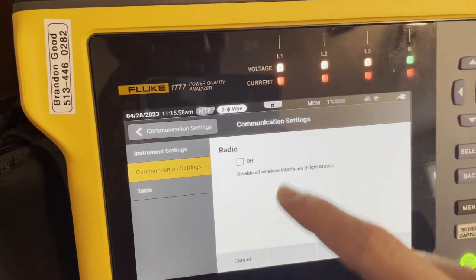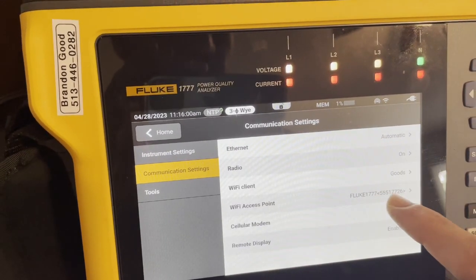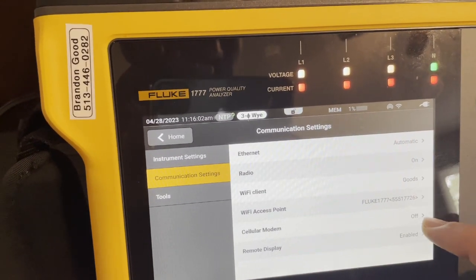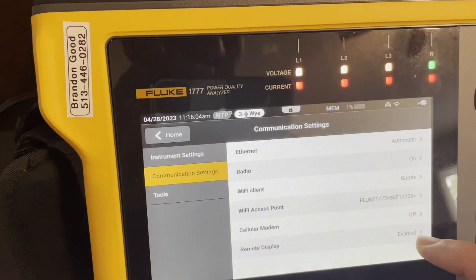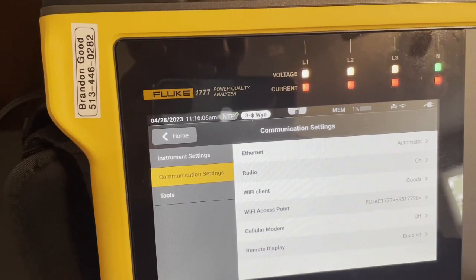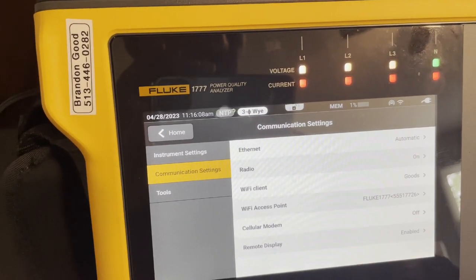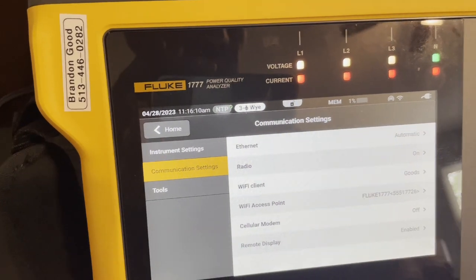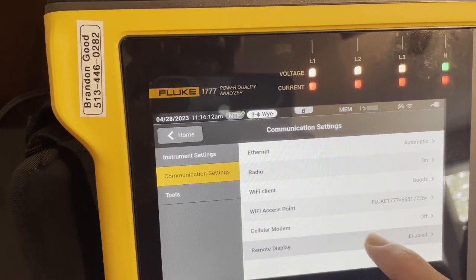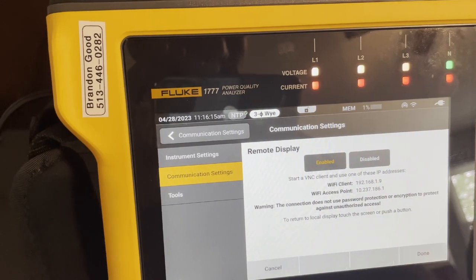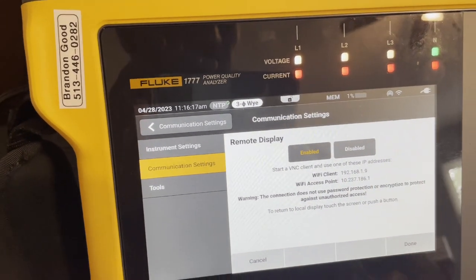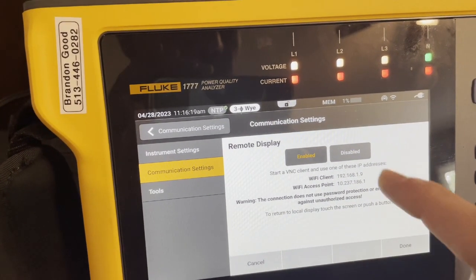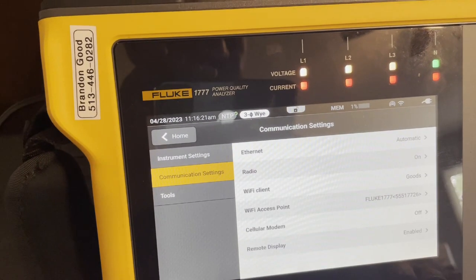Radio. If your radio is off, you might have to turn it on, but I don't think that'll be the case. Obviously, Ethernet, we don't have to worry about. Move down the line. Cellular modem. We don't have a cellular modem in this device. If you do, if I ever get one, I'll try to do a video on that. And then remote display. We do want to have that remote display enabled. Mine defaulted was disabled. So we want it to be enabled.